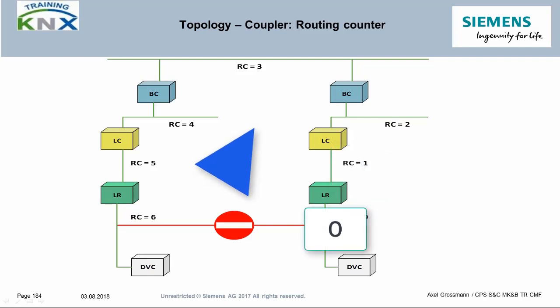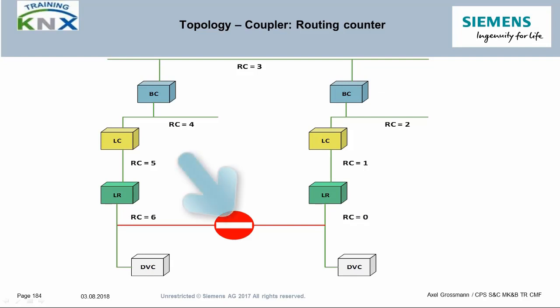If there were no such counter, a telegram would be forwarded endlessly in the case of an electrical connection between two subline segments — only a few such telegrams would crash the system. Thanks to the routing counter, this will not happen. The only thing you cannot do in such a situation is program devices, because all physically addressed telegrams arrive twice at the location of the target device, and the target bus coupler detects this immediately and interrupts communication.